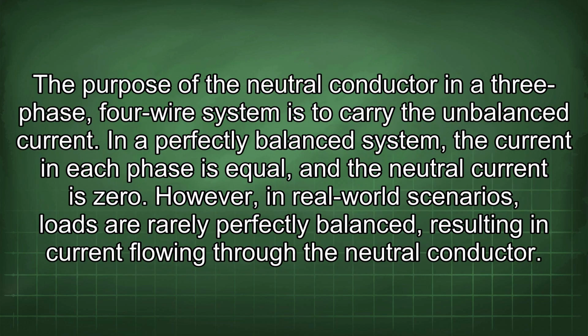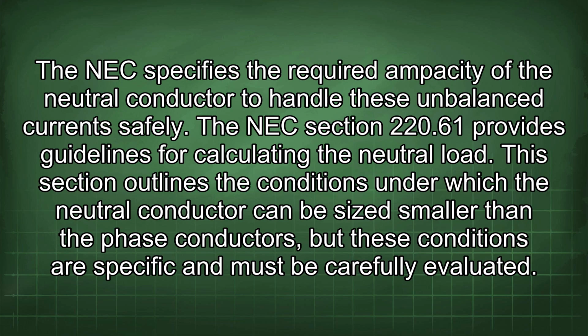The purpose of the neutral conductor in a three-phase, four-wire system is to carry the unbalanced current. In a perfectly balanced system, the current in each phase is equal, and the neutral current is zero. However, in real-world scenarios, loads are rarely perfectly balanced, resulting in current flowing through the neutral conductor. The NEC specifies the required ampacity of the neutral conductor to handle these unbalanced currents safely.